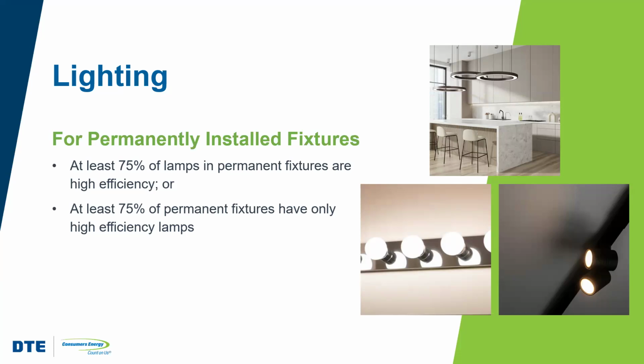So the requirement is that either 3 out of every 4 bulbs in each fixture needs to use high efficacy lamps, or 3 out of every 4 fixtures needs to only use high efficacy lamps. Although technically the first option is available, it's really not likely that one would intentionally mix lamp types in a single fixture. So most good designs are going to have high efficacy lamps in 3 out of every 4 fixtures, if not all fixtures.